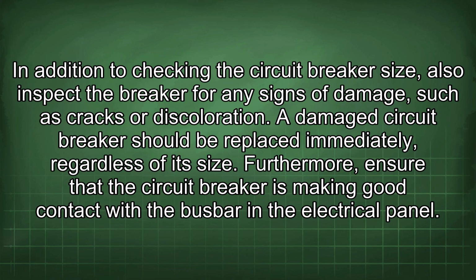In addition to checking the circuit breaker size, also inspect the breaker for any signs of damage, such as cracks or discoloration. A damaged circuit breaker should be replaced immediately, regardless of its size. Furthermore, ensure that the circuit breaker is making good contact with the busbar in the electrical panel.